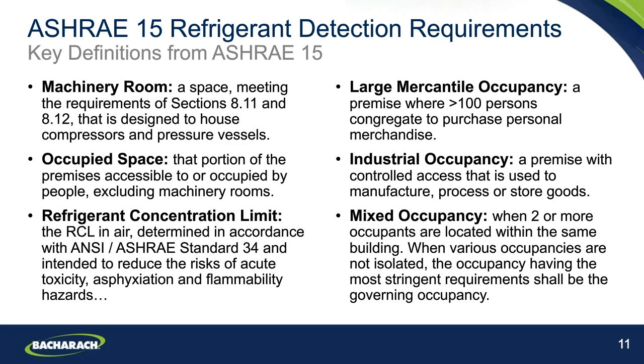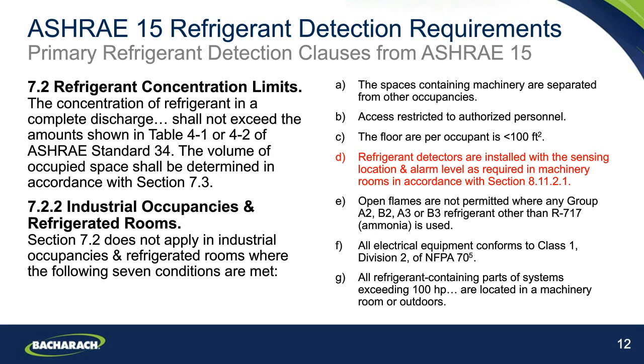So if we look at the clauses within ASHRAE 15 that are primarily reflecting what we need to do on a refrigerant detection level, Section 7.2 defines that the refrigerant concentration limits should not exceed the amounts within ASHRAE Standard 34, which of course can be referenced. What we particularly are pulling out here is that in Section 7.2.2, we see that the refrigerant concentration limit does not need to apply in an industrial occupancy or refrigerated room if certain conditions are met. And as we can see, one of those conditions, which is clause D within here, is having refrigerant detectors installed within the space, essentially meeting the same requirements as are defined very specifically for detection within a machinery room.